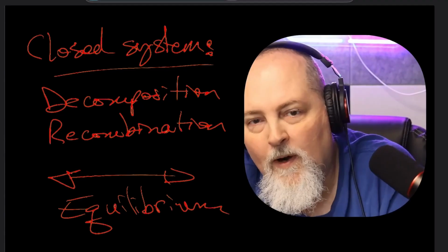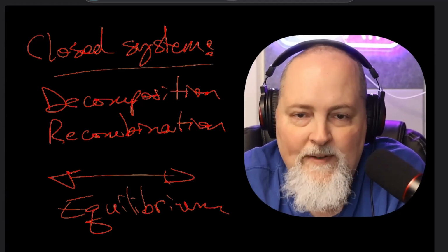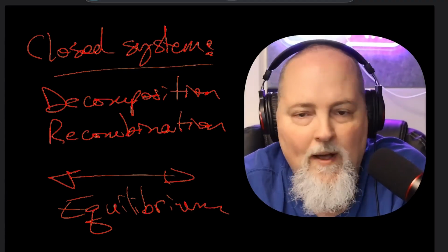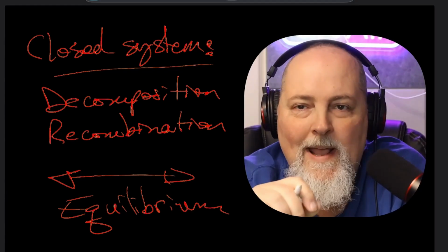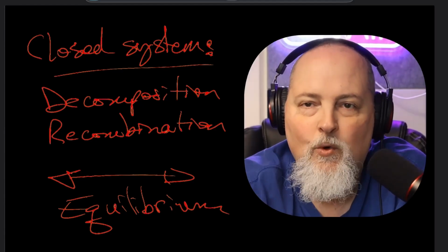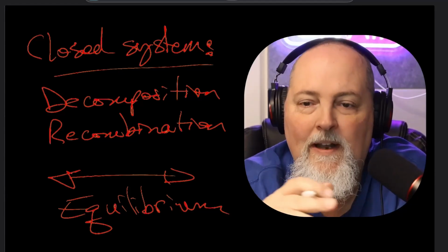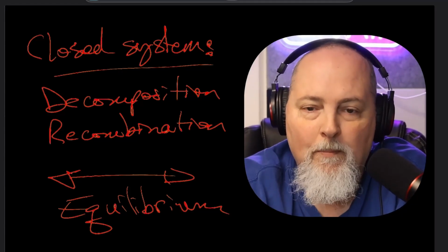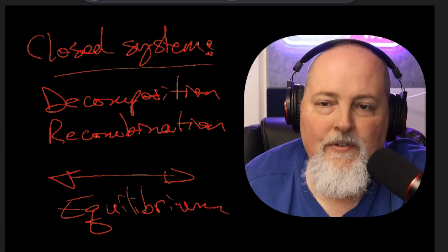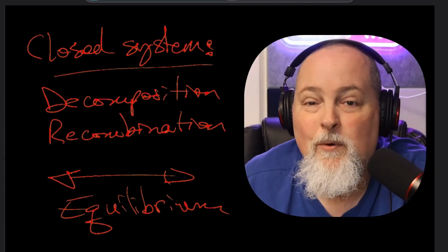So let's shift over and talk about pressurized water chemistry control. In a pressurized water reactor, the goal is to suppress oxygen and reduce corrosion. So we keep the coolant in a desired pH range, and we keep dissolved oxygen extremely low. To do that, we add a little bit of hydrogen. Excess hydrogen shifts the chemistry away from the free oxygen and back towards water. So it helps keep the radiolytic decomposition suppressed. It helps keep the water production going. It helps keep things from forming all these radicals. The hydrogen basically scavenges the oxygen and suppresses the oxidative side of the radiolysis, and so that reduces corrosion risk.